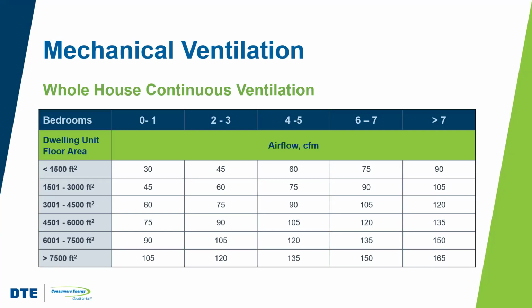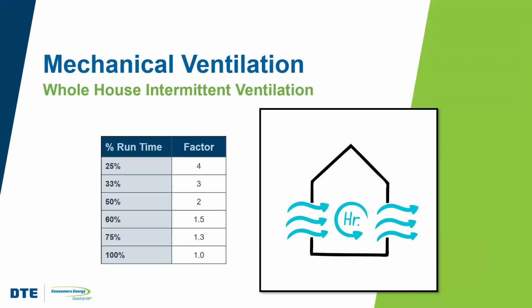Now, regardless of which type of whole house ventilation system is used, for single and two family houses, as well as multi-family buildings with no more than 3 stories above grade, the minimum continuous whole house ventilation rate is based on the conditioned floor area and the number of bedrooms. Now, as with local exhaust systems, when the whole house system operates intermittently, they have to provide higher ventilation rates to compensate for the reduced operating hours. So for every 4-hour period, an intermittently operating system has to provide the same ventilation rate as what would be provided under a continuous operating system.